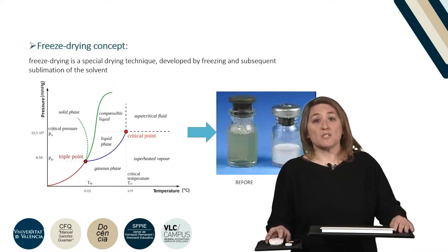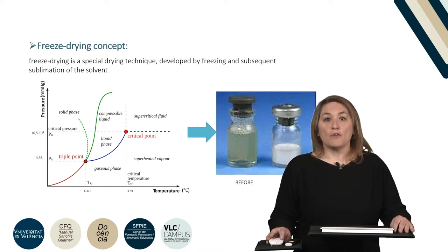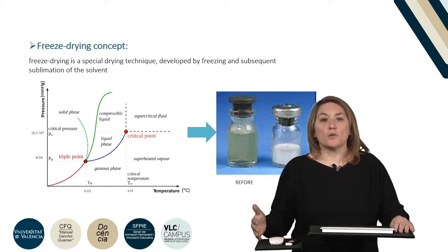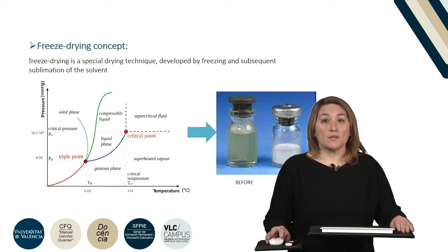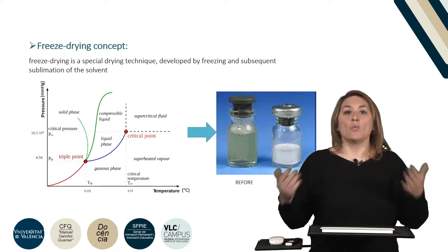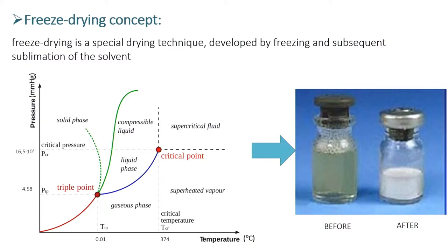Freeze drying is a special drying technique applied to a solution, freezing the solution and afterwards eliminating the solvent. This solvent, which in most cases is water, will undergo a process of sublimation in a vacuum environment — that means that ice will turn into a gas which will be subtracted from the chamber. The product obtained has a porous texture and lyophilic character, that is, it has a great affinity for water, which allows a fast and complete reconstitution to the initial product.